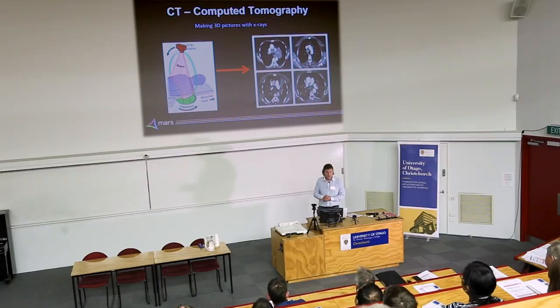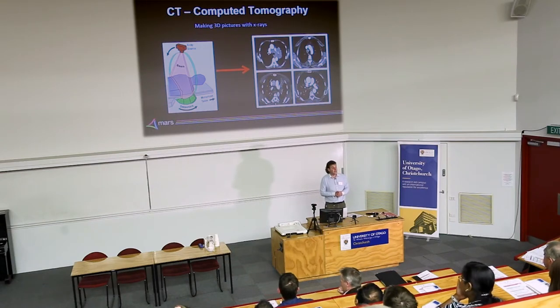With our scanner and other photon counting systems, you take the same broad spectrum of energies from the x-ray tube, they're attenuated by the patient, and then a key photon counting detector separates them into different energy bands — giving you multiple points on the linear attenuation curve. That allows you to start identifying the materials in the object.